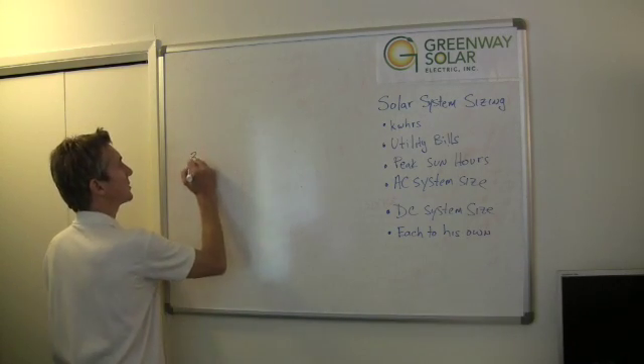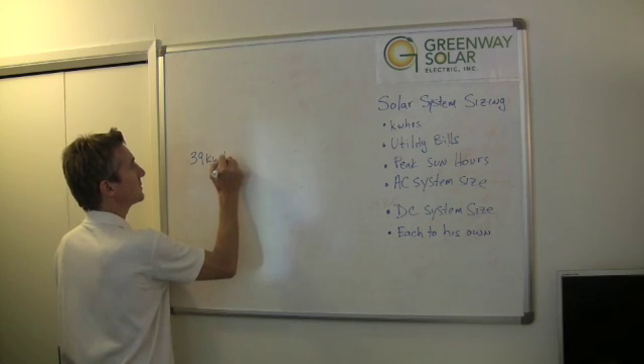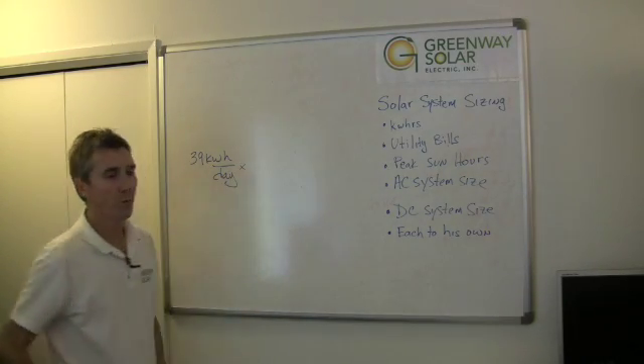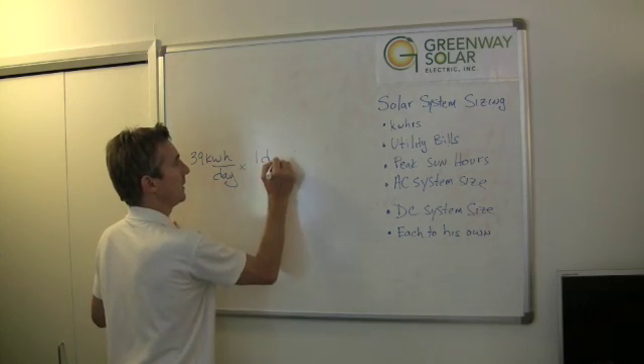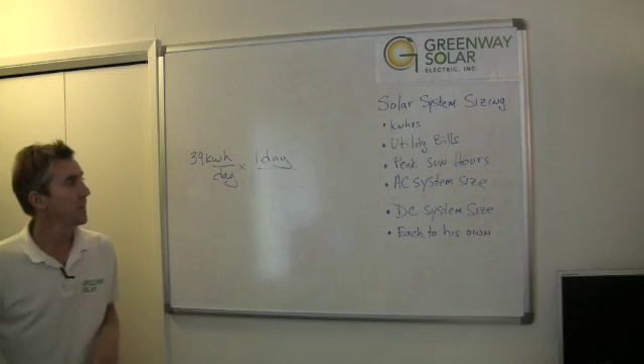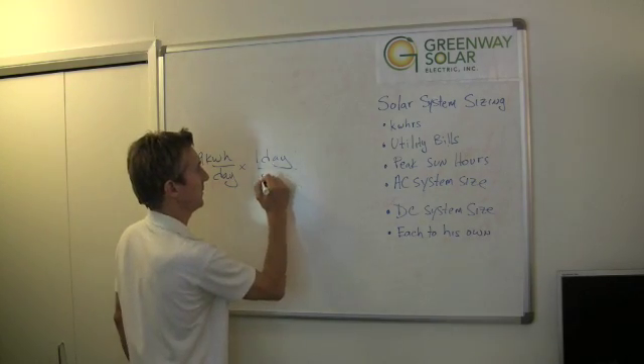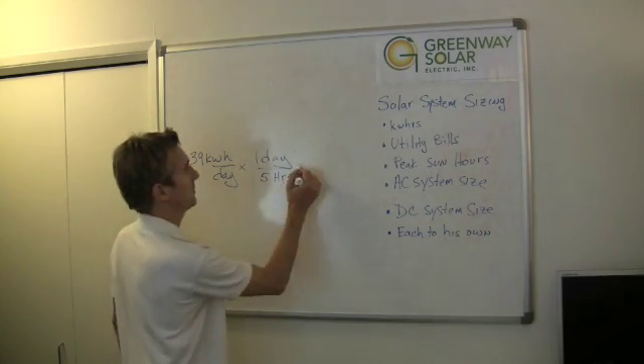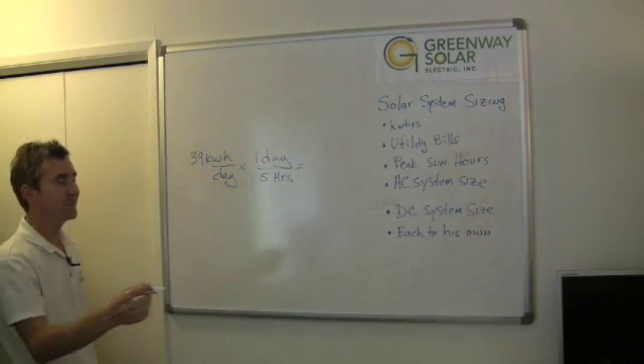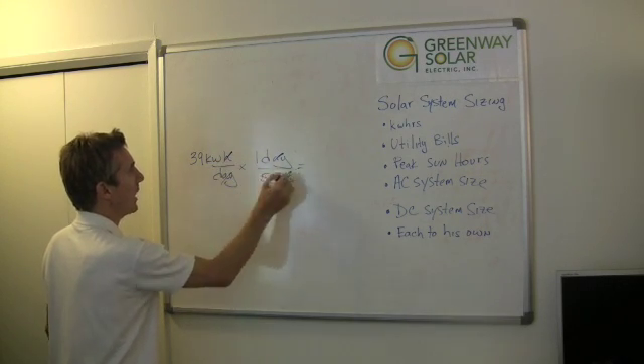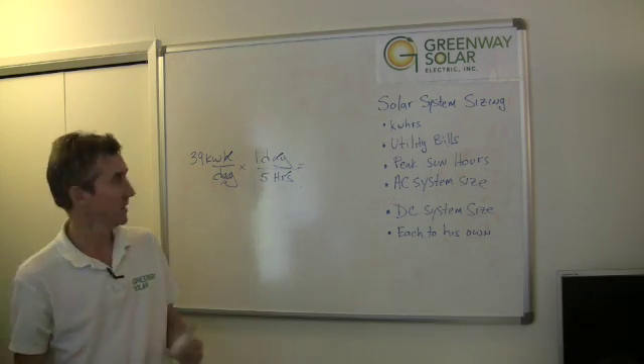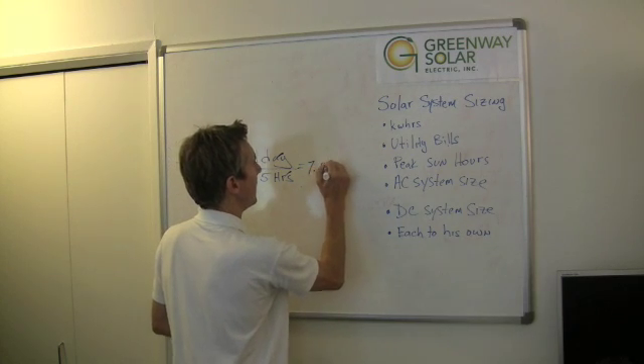So let's take, for example, the customer who uses 39 kilowatt hours per day. So we just said in one day they receive about five peak sun hours. Five hours. So I'm going to use a little bit of cancellation here. One day, one day. This is an hour, an hour. If I divide 39 by five, let me get my calculator out. I can probably do that in my head but just to be exact. 39 divided by five is 7.8 kilowatt.